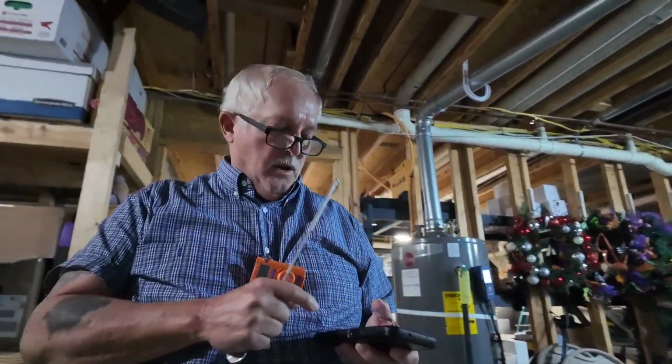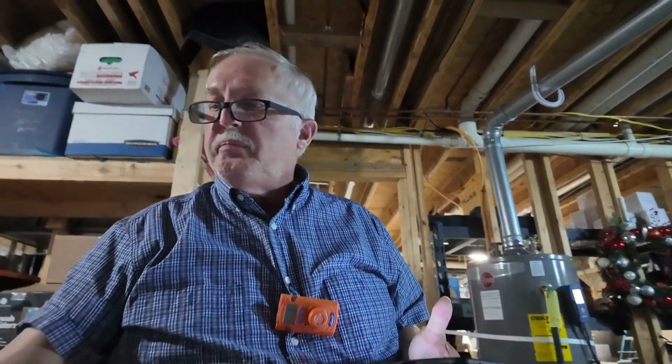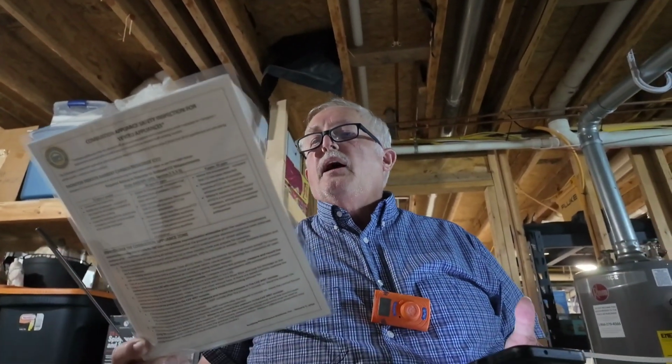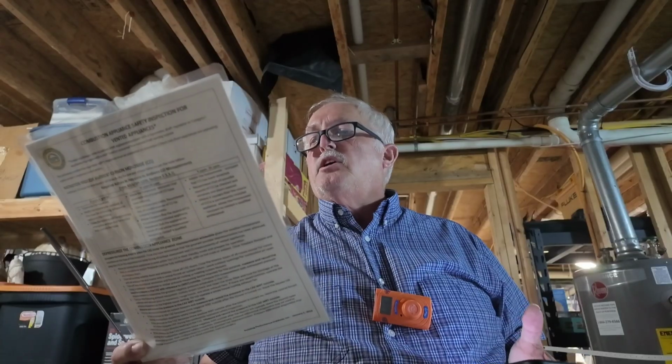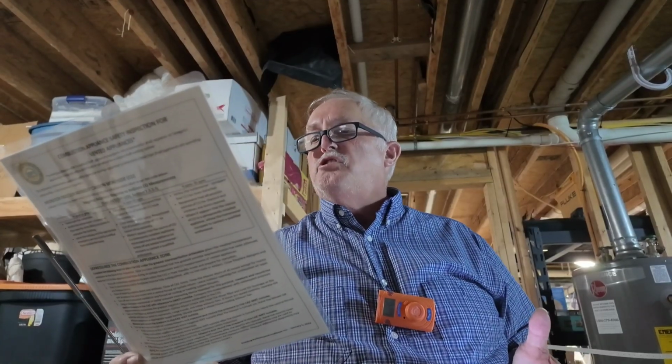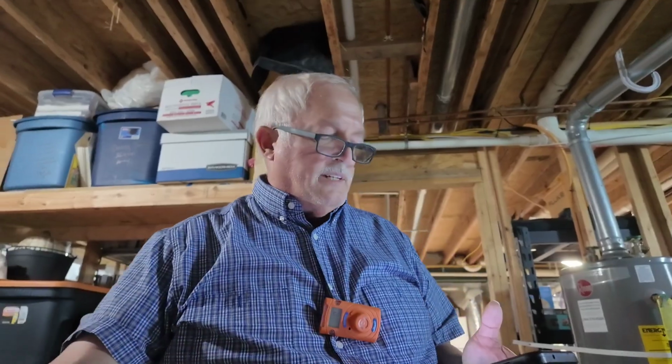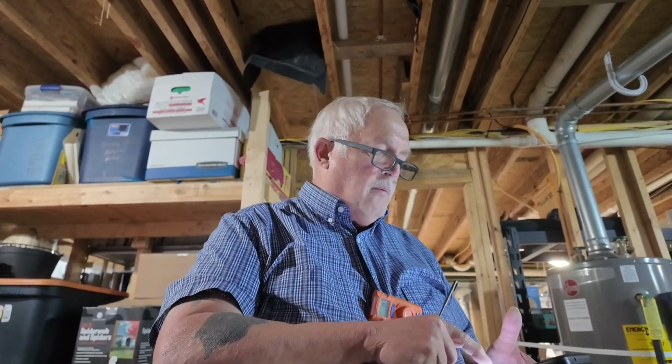According to our guide, action levels for spillage occurring at 2 minutes of main burner operation. Well, it quit spilling, but if it had not, I would refer to the action tables in this particular guide. The next, it says that I need to measure CO in undiluted flue gas at 5 minutes of main burner operation. Well, since I've already been running for 2, I'm going to set it at 3 minutes, and I'm going to hit the timer.